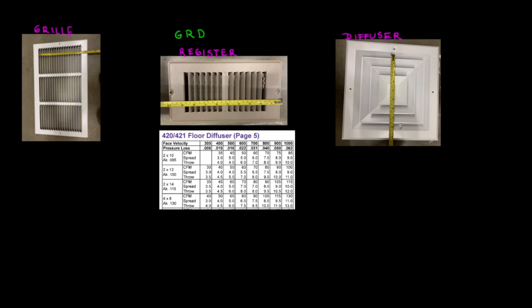The most important part of these air devices is that we need to control velocity. For commercial applications, we also need to consider NC, which is noise criteria. We need to find a perfect balance because more velocity means more noise. For grills, it's recommended to have the velocity between 300 to 500 FPM — feet per minute.